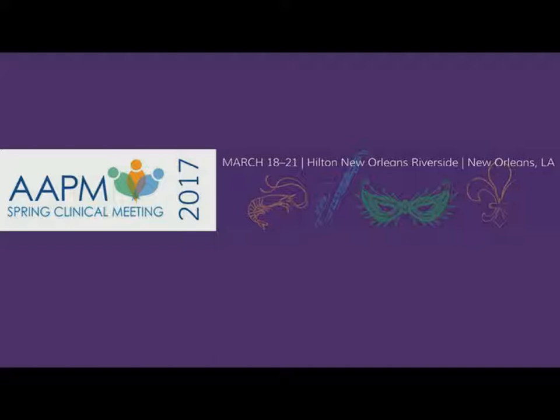The question is when you don't have the real drawings. In other words, you can't get old drawings, correct? You have unreliable drawings, let's say, or you don't know how good they are. Ideally, we had this situation the other day where they didn't know whether the drawings were correct or not. They still had the old linear accelerator in there, and we had to make some transmission measurements with the existing linear accelerator, because you can back calculate how thick that is based on those measurements. If not, you pretty much have to decide.